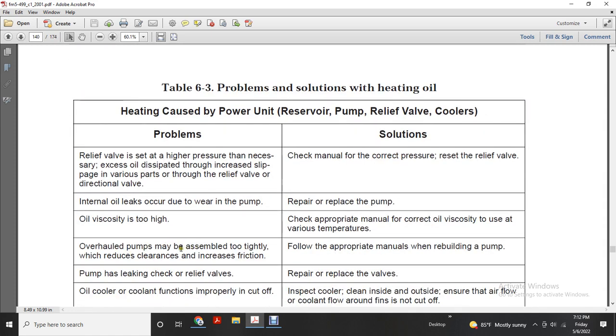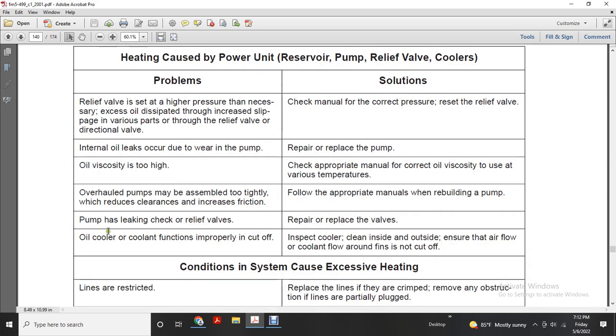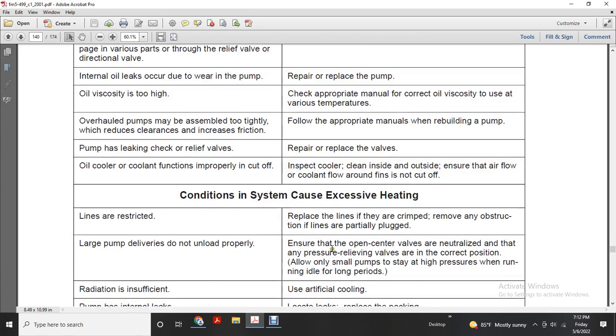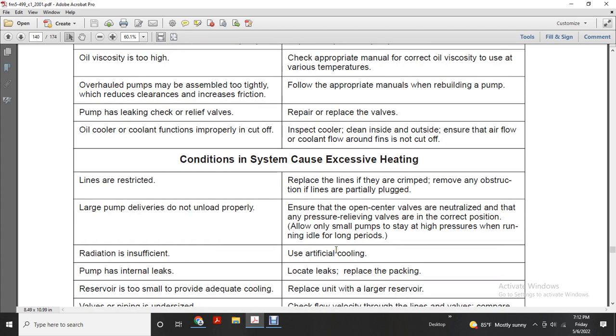Overhauled pumps may be assembled too tightly, reducing clearance and increasing friction. Follow appropriate manuals when rebuilding a pump. Pump has leaking check or relief valves. Repair or replace valves. Oil cooler or coolant functions improperly or is cut off. Inspect the cooler, cleaning inside and outside. Ensure the airflow or coolant around the fins is not cut off. Cooling condition of the system is causing excessive heating.